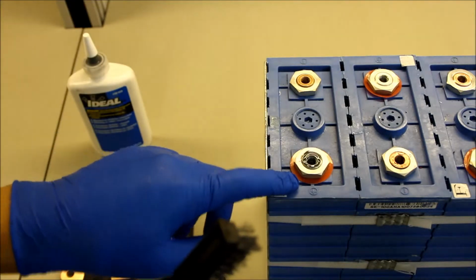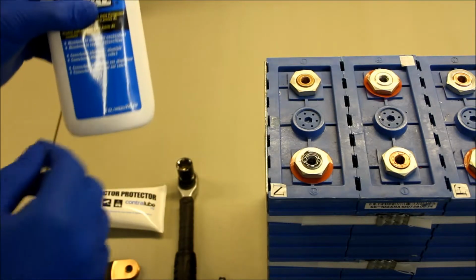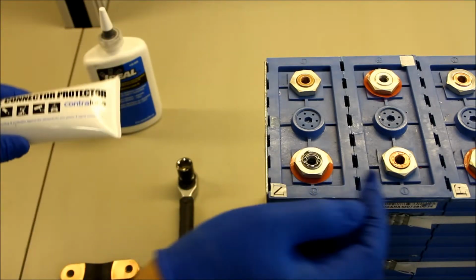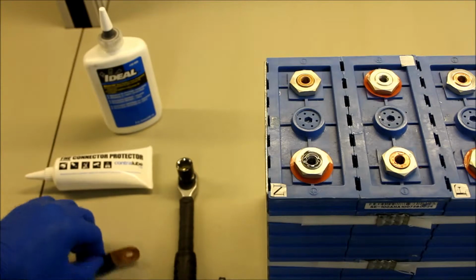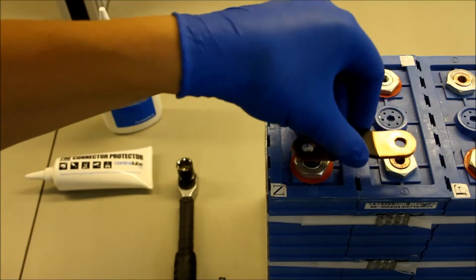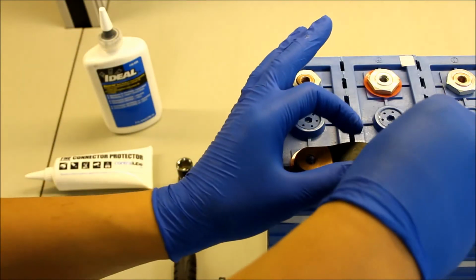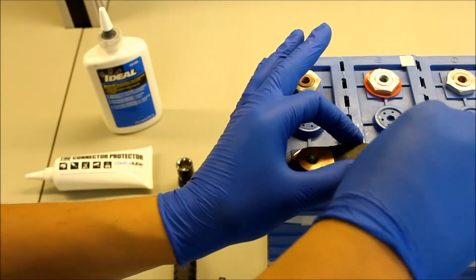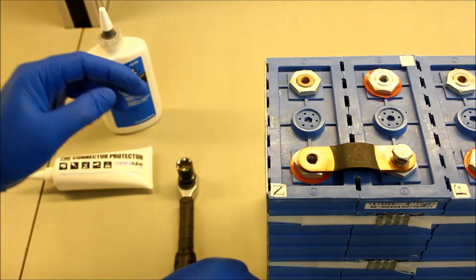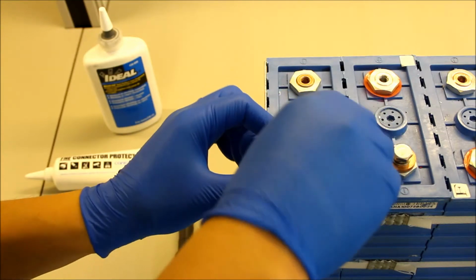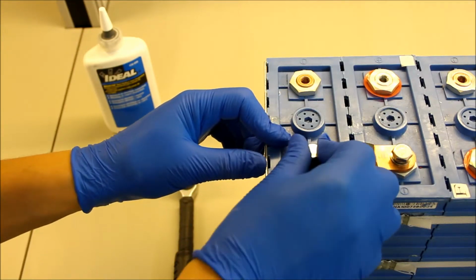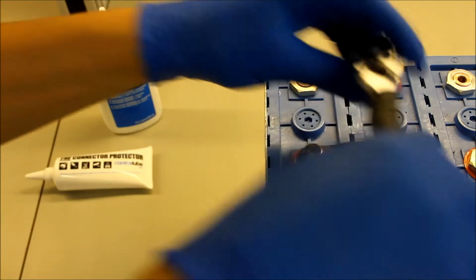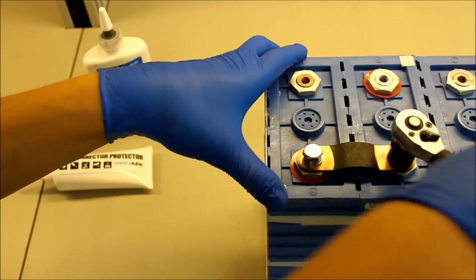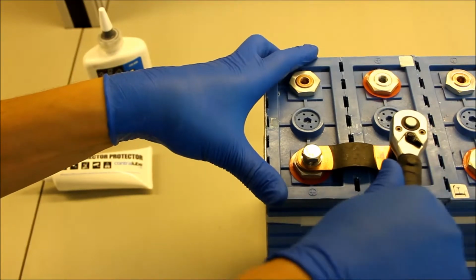So I've cleaned the bus bars with our wire brush and also the cell terminals. I've applied some compound to the aluminium terminal and also some other compound to the copper terminal on the cell. I'll now take my clean bus bar, put it in position carefully, take our stainless bolts with spring washers, and apply torque to the manufacturer's recommended level, which in this case is 14 Newton meters.